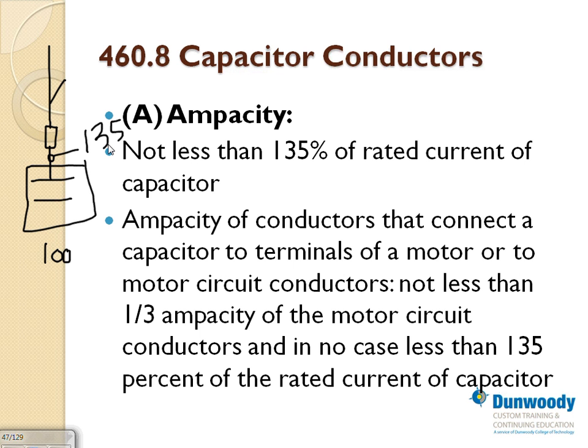The fuse, they tell you the fuse has to be as low as possible. I usually size it to match the overcurrent protection device. So I size my conductor at 135. It's not a standard fuse size. You're going to go down to 125, which is a standard fuse. So I can put a 125 amp fuse on that.